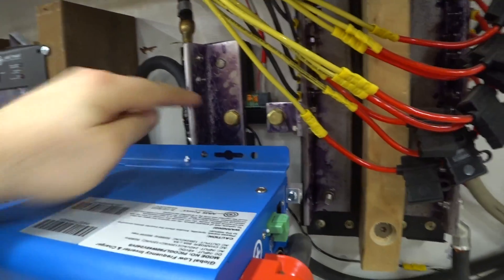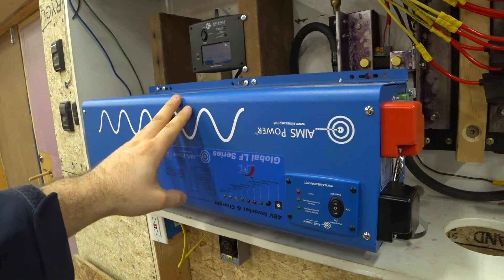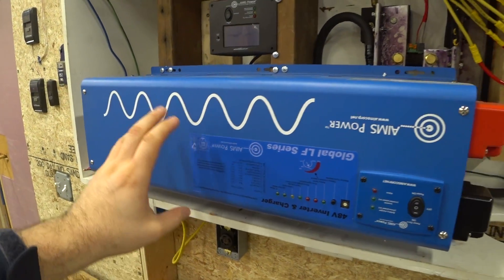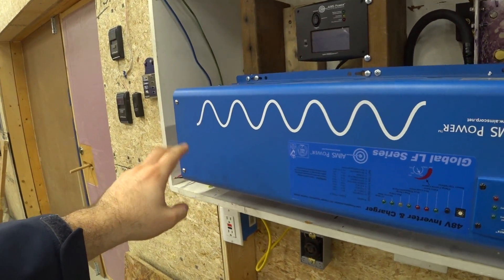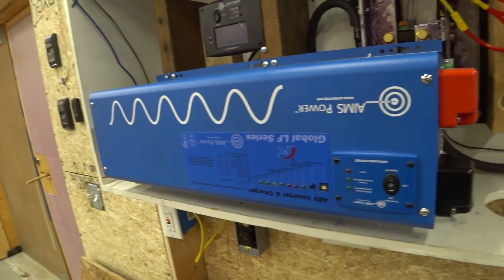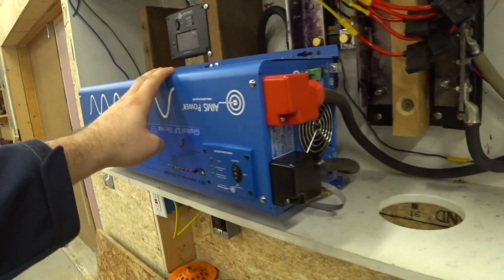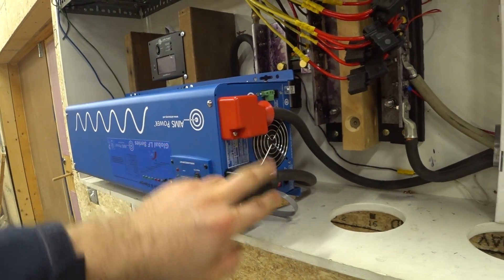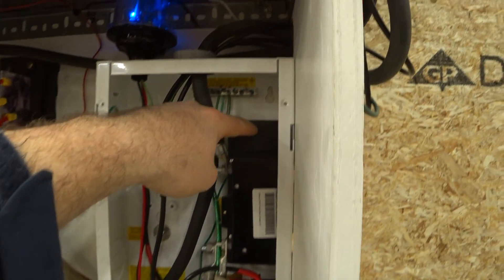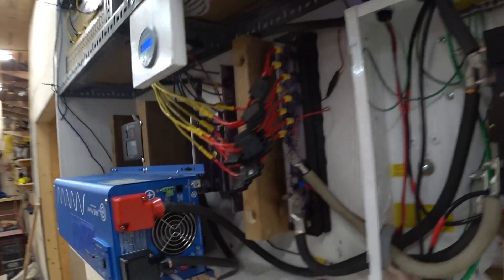This inverter is made by AIMS Power and it's a 6,000 watt low frequency inverter, meaning there's a big transformer inside. It supplies 120 volts alternating current on two legs, which can also be combined to 240 volt alternating current — the normal electricity used here in Massachusetts. The big positive and negative are supplied using 4-aught cable, which goes through this big 250 amp breaker.